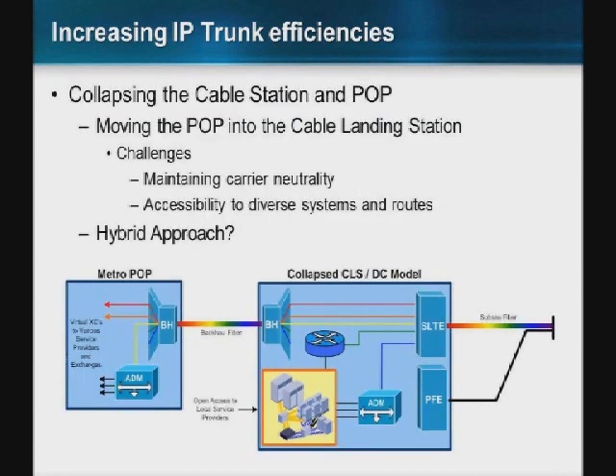The other approach is to go in the opposite direction — build a data center in the cable landing station. A classic issue is that cable landing stations are typically closed environments, so how do you maintain carrier neutrality and access to diverse systems and routes? However, given the limitations on viable landing points, most cable landing points are clustered. So maybe not in the same physical building, but within a few kilometers, you have access to diverse systems — it's just a matter of organizing an approach to gain access and interconnect to those systems to get the diversity you need.